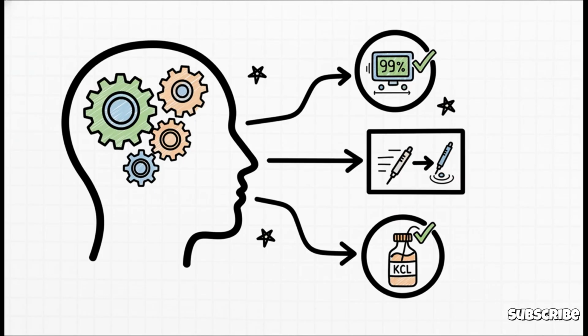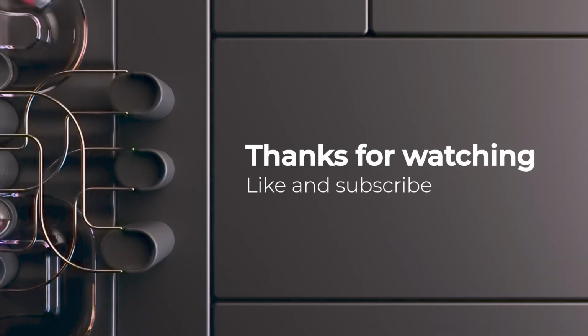So let's just wrap this all up. What's the expert's mindset? It's not about memorizing 100 different rules. It's simply about respecting the science behind the tool. It's about fundamentally understanding that you're not using a rugged thermometer, you're using a delicate, sensitive voltmeter. So what does that mean? It means you always calibrate correctly, and you always check that slope. It means you always use the move-then-still technique to get stable readings. And please, for the love of good science, never, ever store your probe in plain water. At the end of the day, the question you have to ask yourself every single time you go to take a reading is this: am I actually measuring reality, or am I just fooling myself with a number that just looks right?